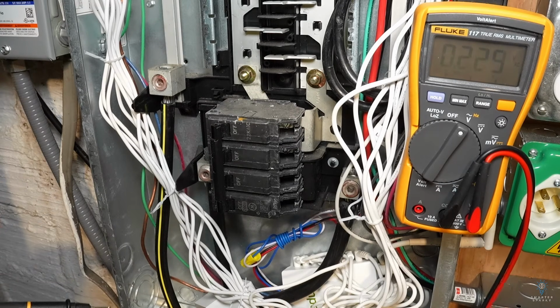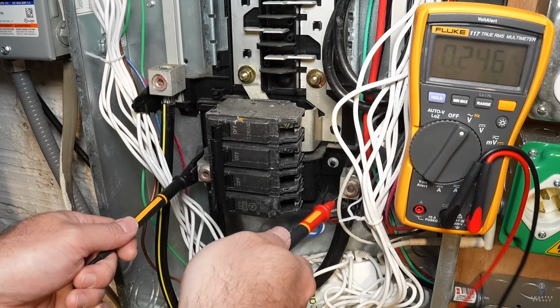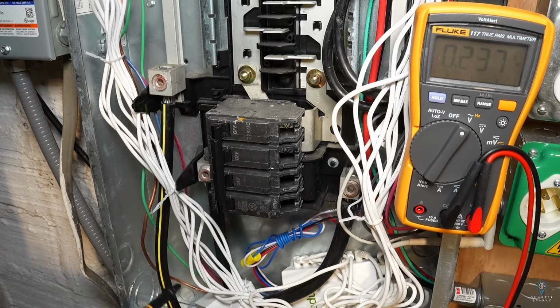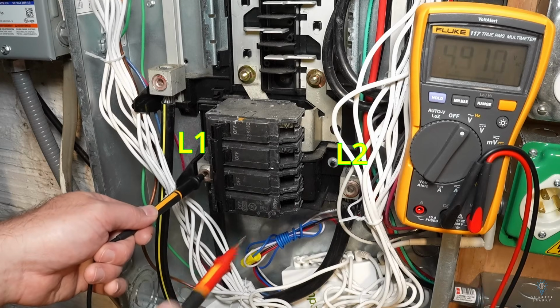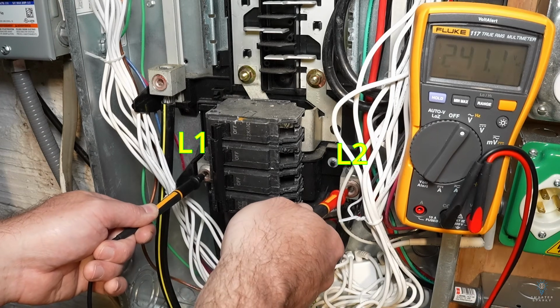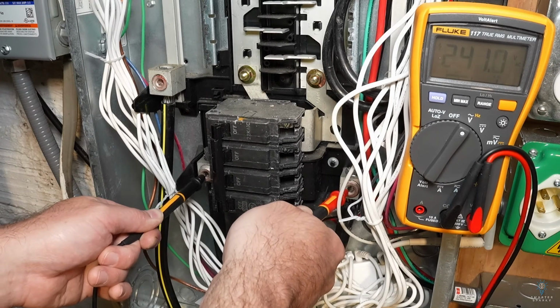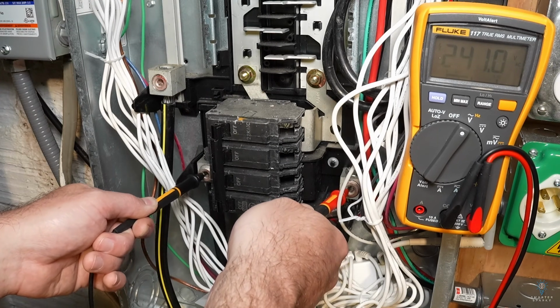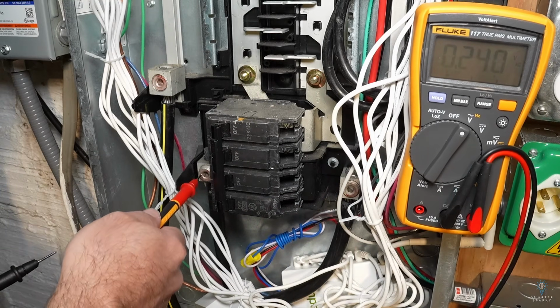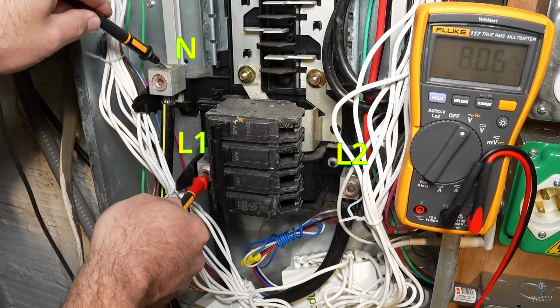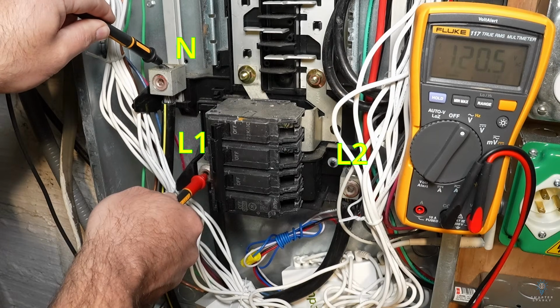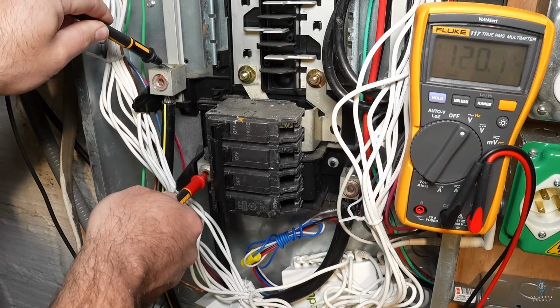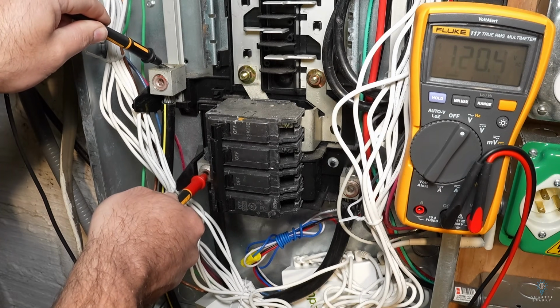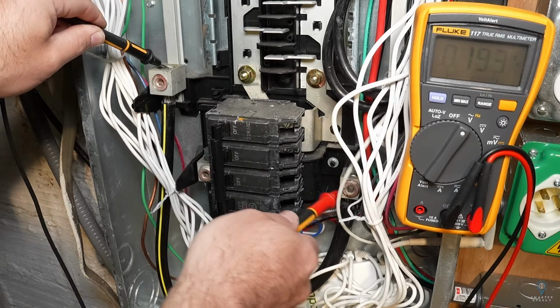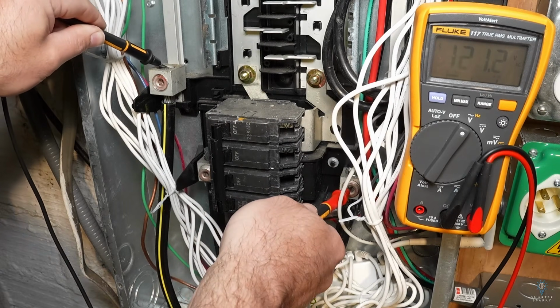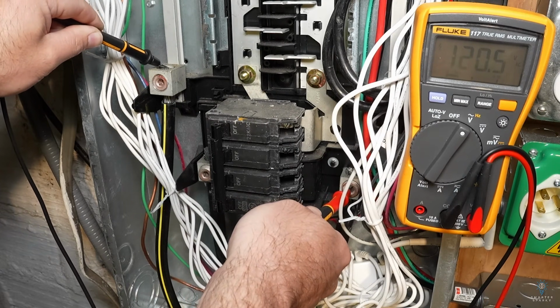So I'm going to start by taking a couple voltage measurements here. These two lugs right here are going to be the two lines coming in. So from line 1 to line 2, we should have 240 volts. And it looks like we do. That's a pretty solid connection right there. But where things start to waver is when we go from line to neutral. And this is where we start getting those voltage differences. Now there we've got exactly 120 volts. And from neutral to, let's say this is line 2 over here, we've also got 120 volts. Interesting.